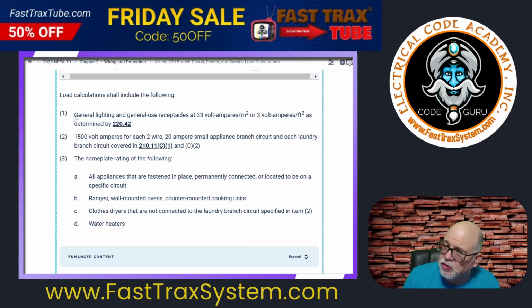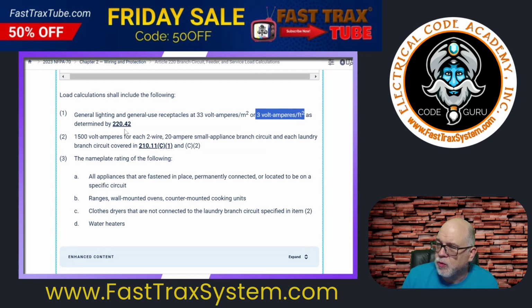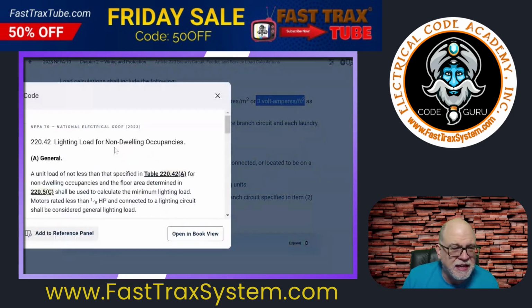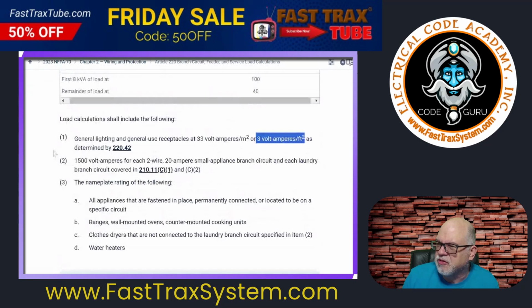First thing you got to do is calculate the general lighting and general use receptacles at 3 VA per square foot as determined in 220.42. I'll click that so you can kind of see, and a little bit of it will pop on the screen. Again, this is where it talks about lighting for non-dwelling loads, but not really significant for us here.